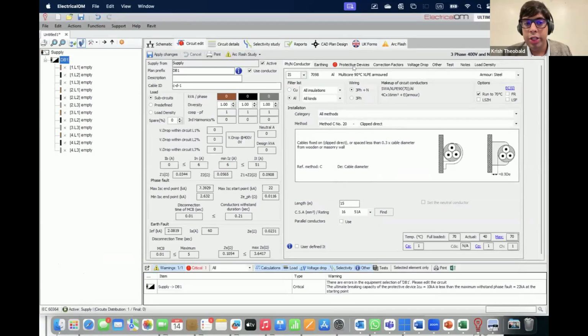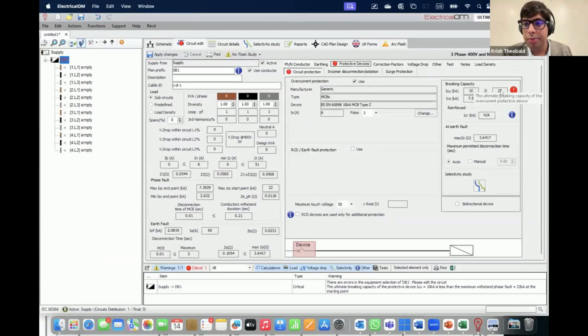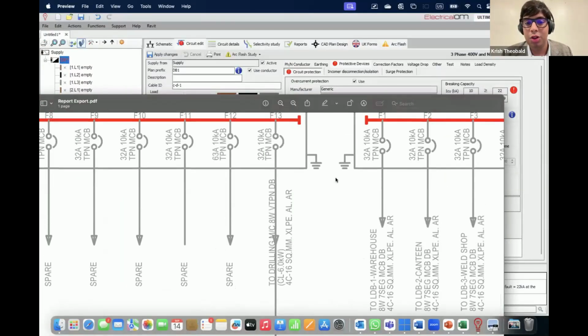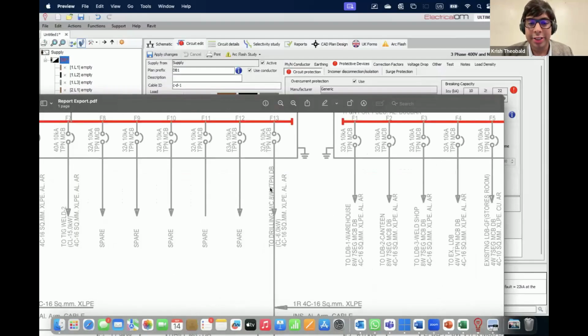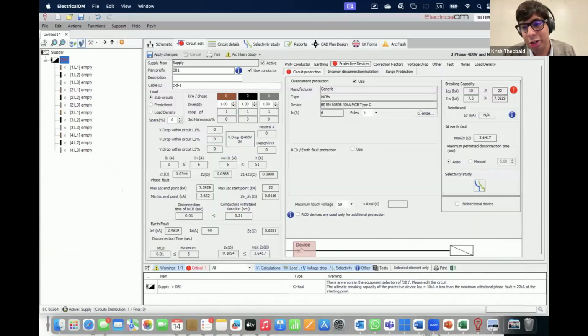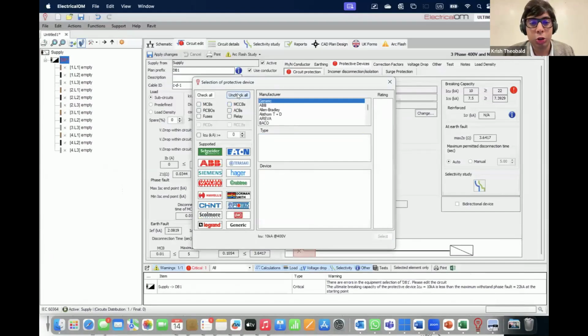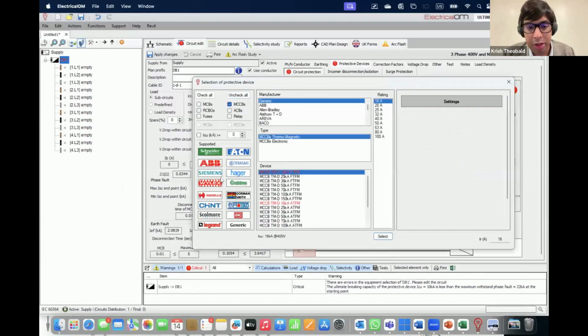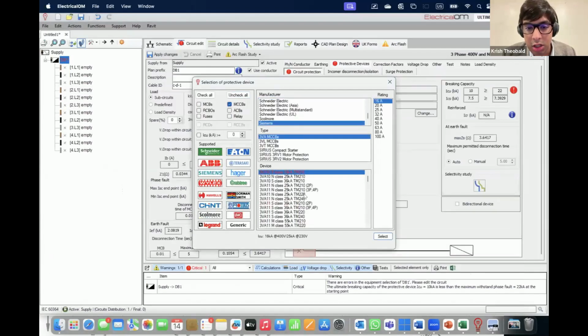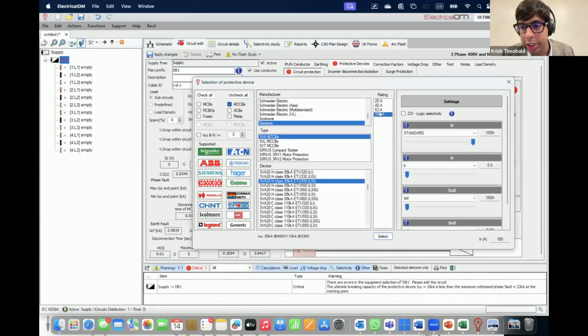Now you see the software is immediately giving me a warning because at this point I've got 22 kiloamperes of short circuit current that is possible, but the current default device can only do 10. Okay, so in this case it's an MCB, but because we have assumed a higher short circuit current, we're just going to select an MCCB in this case. So uncheck all, MCCB. Let's say, for example, it's a Siemens, and let's select a nice little ETU 350 product, set it to 100 amps, and we will down set it to say something like 53.